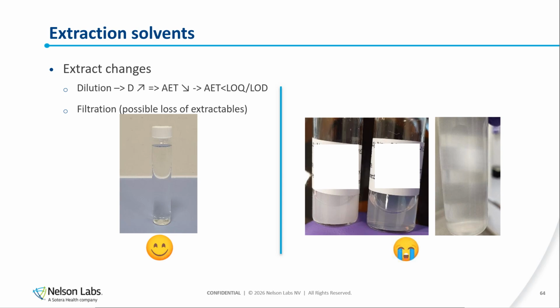So what can we do there? We can dilute the extracts, but of course, increasing the D factor will reduce the AET. And as you know, with the 3 figures before, your AET will go lower and lower, and perhaps go below the LOQ or LOD of the instrument, and you have a new problem.